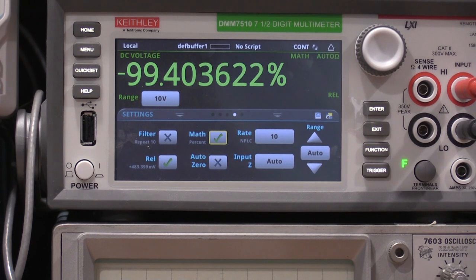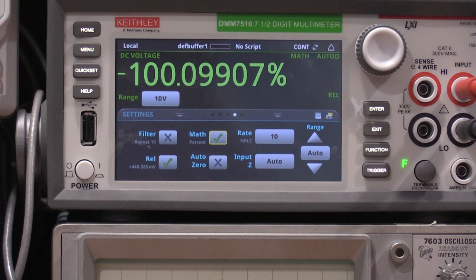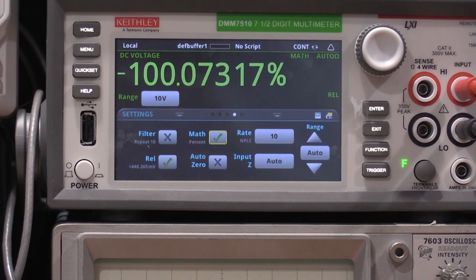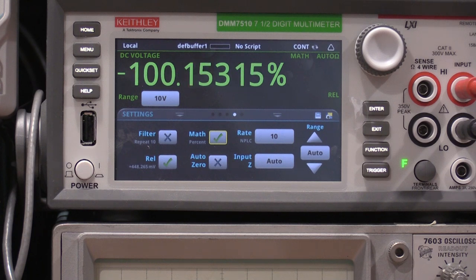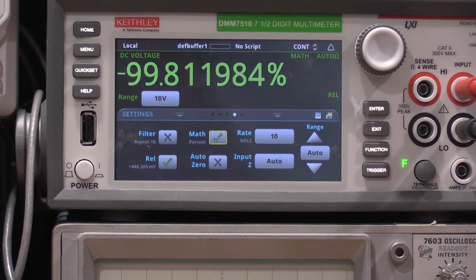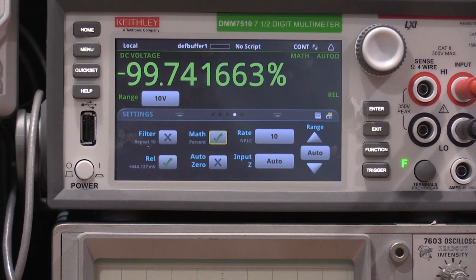It wants me to check a higher voltage, so I need an attenuator. Why don't we check a 4.7? That one's fine. Yeah, that range is good. Yeah, that range is good. Yeah, that range is fine. Yeah, that's fine. Much more stable at a higher range. I'm on to the 25 by 50. Nope. Bumped the control. That's fine. Check it relative to 50. And then we'll wind up on the highest range. Excellent. Within a percent. So I am happy with that.